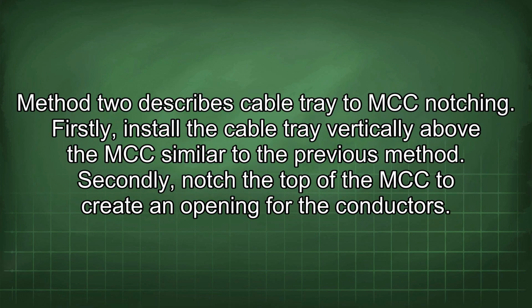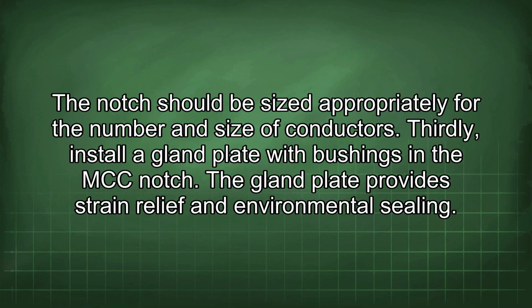Method 2 describes cable tray to MCC notching. Firstly, install the cable tray vertically above the MCC, similar to the previous method. Secondly, notch the top of the MCC to create an opening for the conductors. The notch should be sized appropriately for the number and size of conductors.